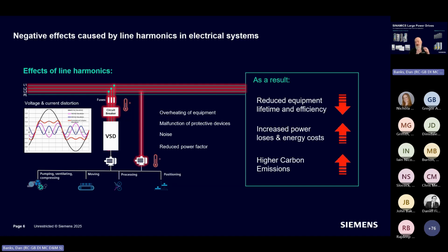They are everywhere. Almost every piece of electronics we use at home now, with the possible exception of a kettle, is a non-linear load. And that means that background noise that maybe 20 years ago, when we were still using filament bulbs and CRT TVs, has lifted up significantly. And then on top of that, we've piled renewable energy, solar power. Solar generators are all variable speed drives. Every single wind farm we see has got an inverter in it. So this background noise is lifted up, and that's why I'd say over the last 5 or 6 years, harmonics has really risen to the top of the issues.